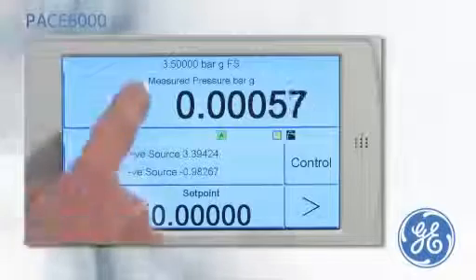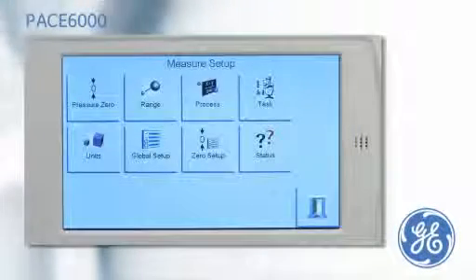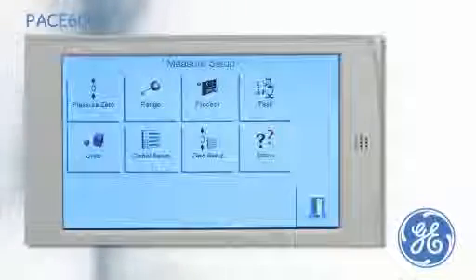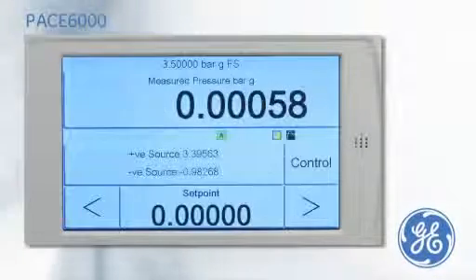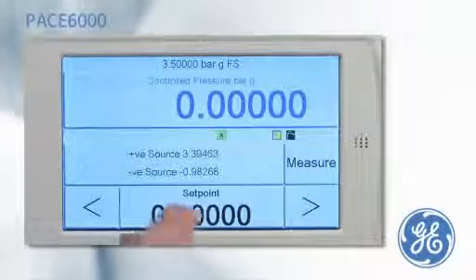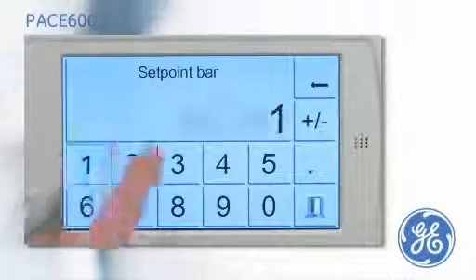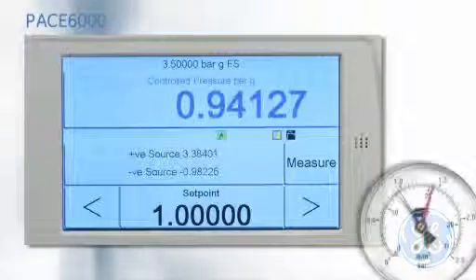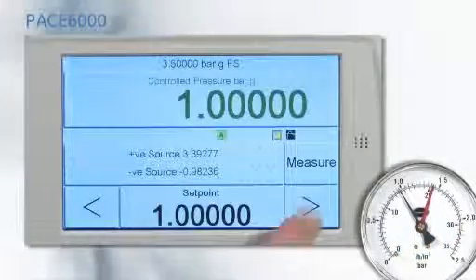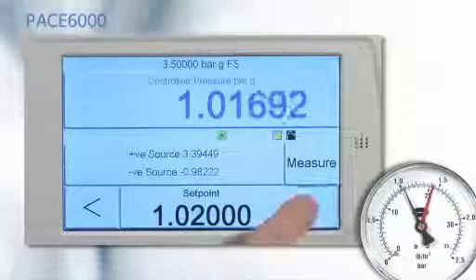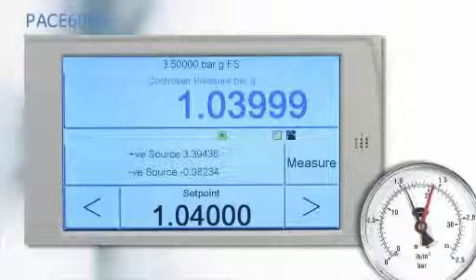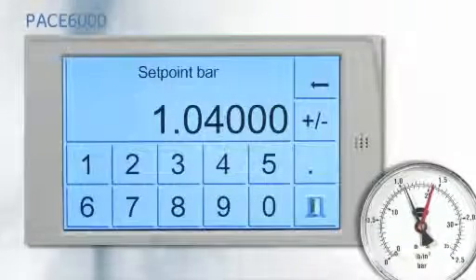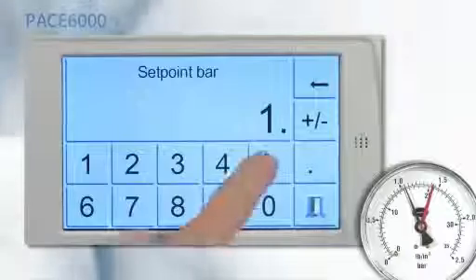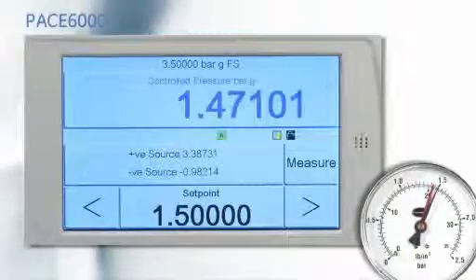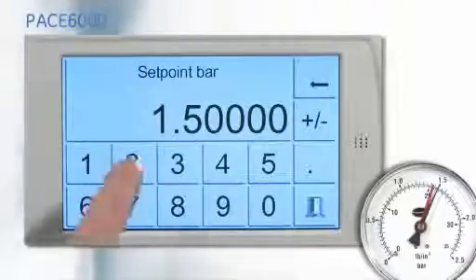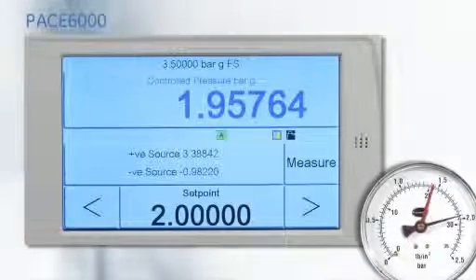The PACE6000 is designed with an easy-to-use task-driven menu. To calibrate a pressure gauge, select the basic task, put the PACE into control mode, enter the set point. Once the PACE has achieved the set point, the display will turn green. The nudge button can then be used to line the gauge pointer with the dial marking before noting the pressure applied. Enter the set point to the next cardinal point. Repeat until the calibration is complete.